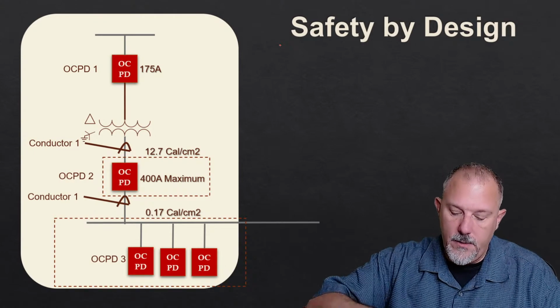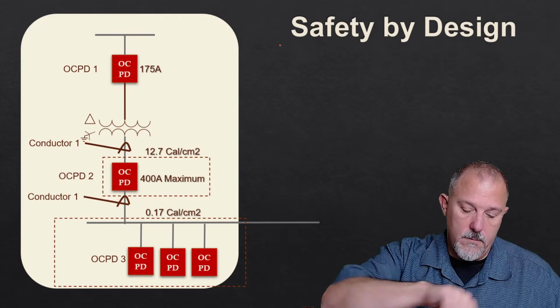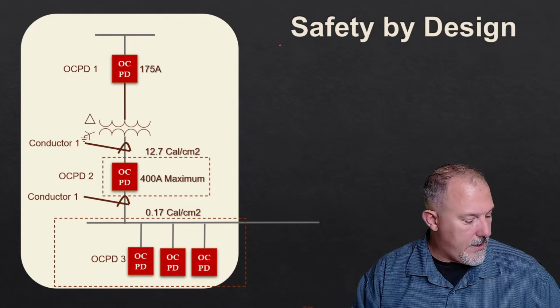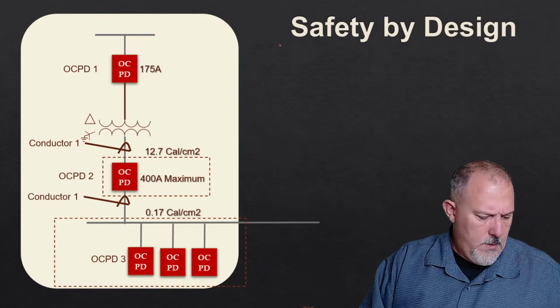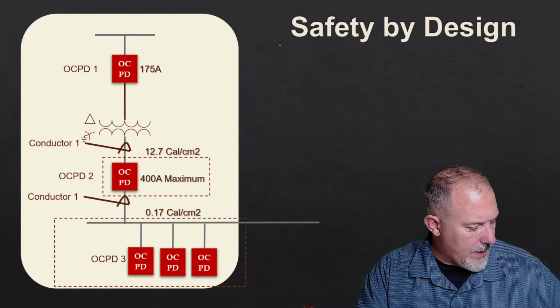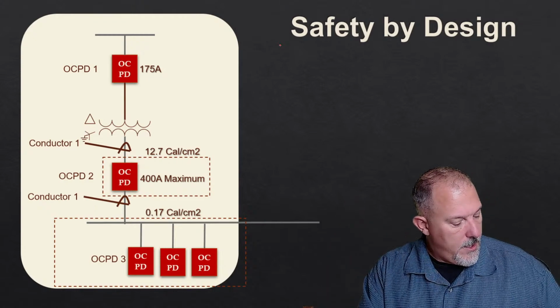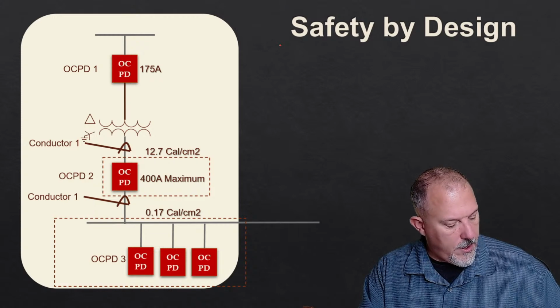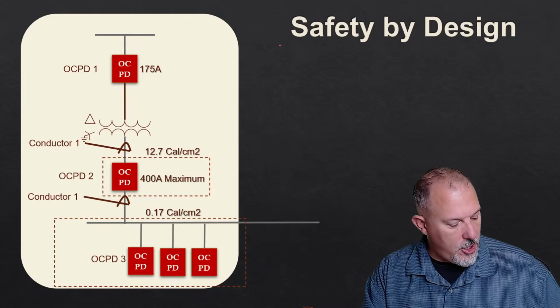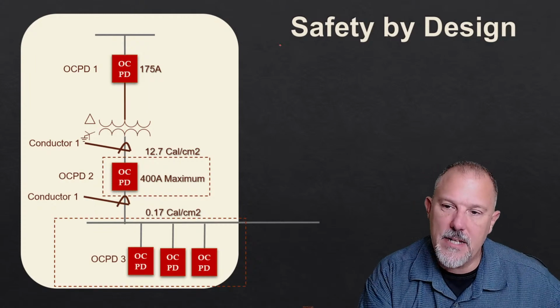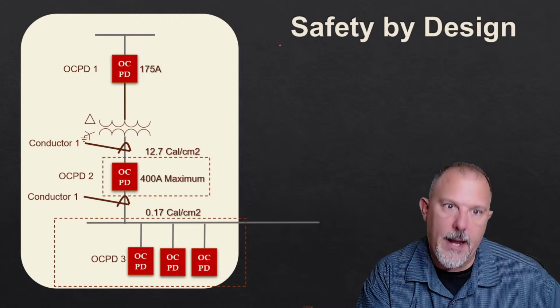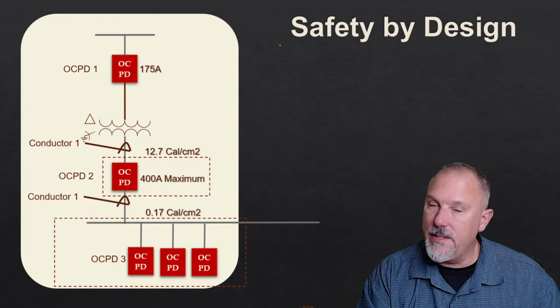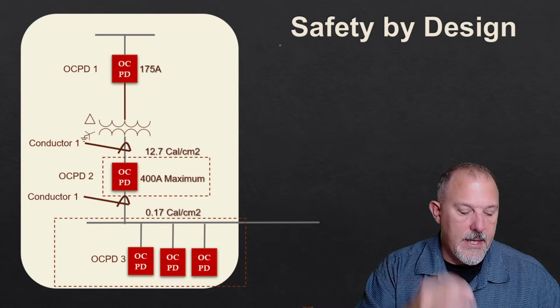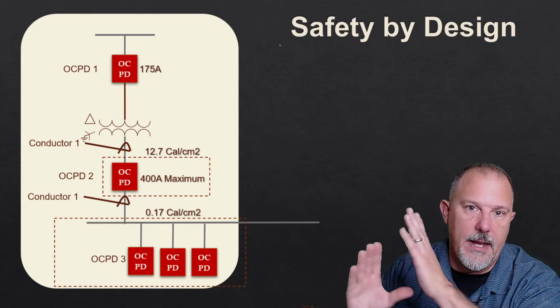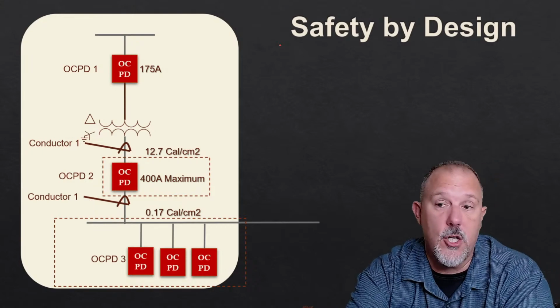110.28. Where is it at? 110.28, enclosure types. Enclosures, fences or walls covering other than of switchboards, switchgear, panel boards, industrial control panels, motor control centers, meter sockets, enclosed switches, transfer switches, power. So Felix, I think it's because of the language, because they said enclosures, and enclosure is a defined term. It points you over here to 110.28. I think you're not going to be just compartmentalizing within, say, a panel board, switchboard, or anything. It says enclosure.